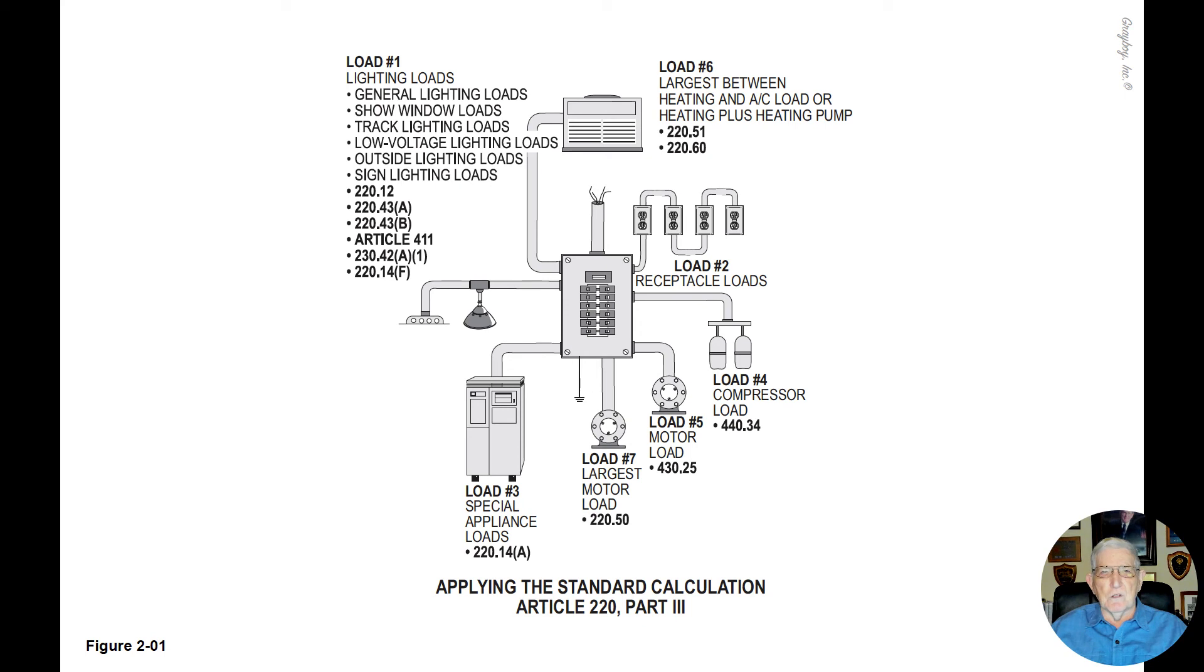Most of the time you would choose the largest motor, then you would take 25 percent of that and add that to the total load if you were sizing the service. But for the sake of this test taken made easy workbook, we're breaking each one of these loads down to individual loads instead of you having to add all the loads together.